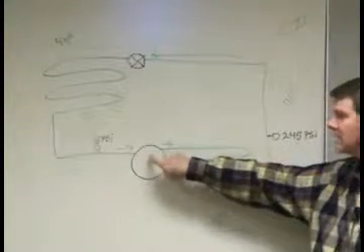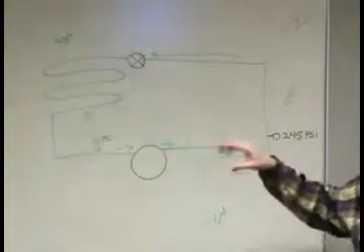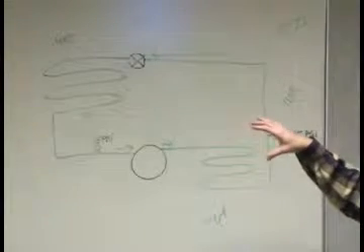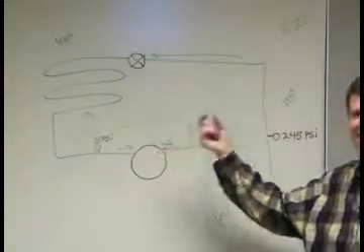Advantage of that is in a normal air conditioning mode, I talked about at the beginning, this compressor adds a lot of heat to that gas going through it. Just heat of compression and all the mechanical, electrical heat that's generated by the compressor gets added to that gas. When you're using this as a heat pump to heat with, that's a good thing. You can use that heat.